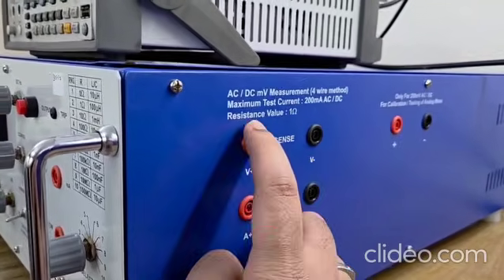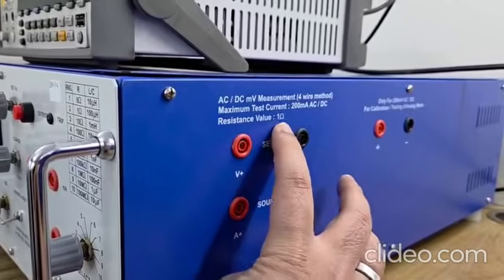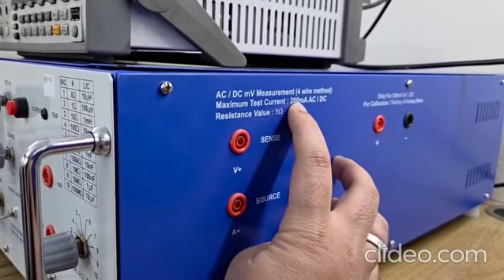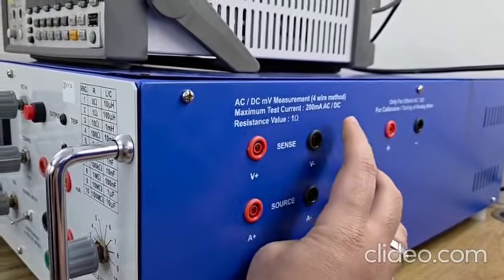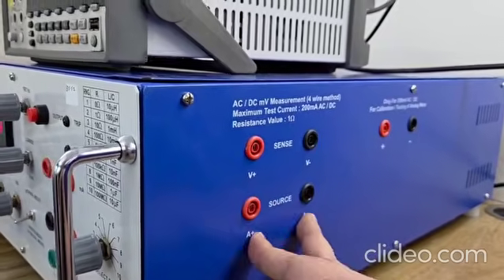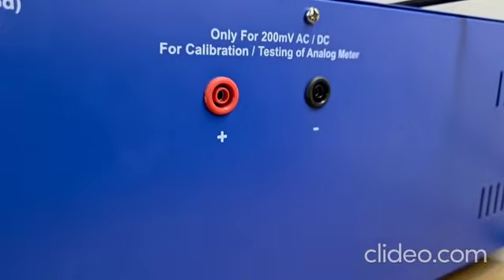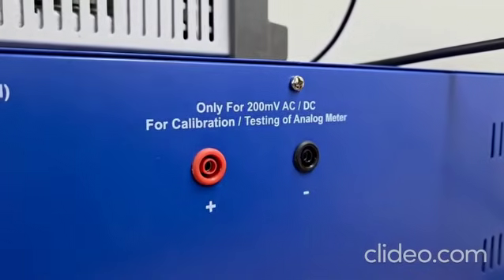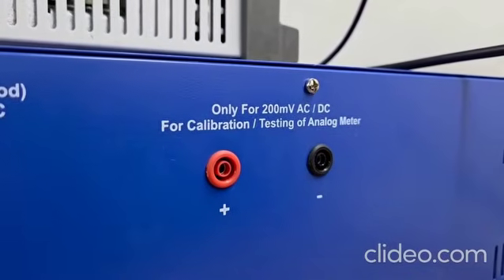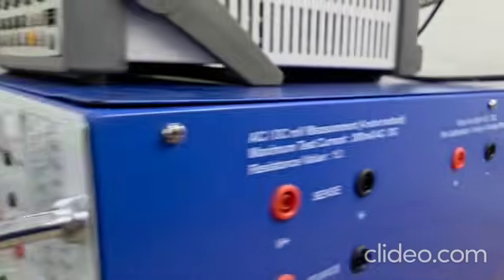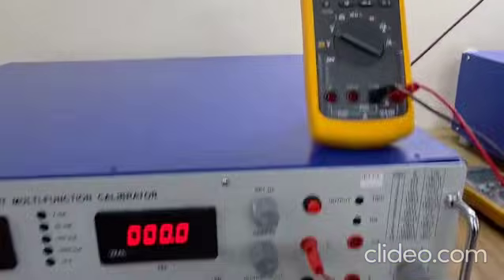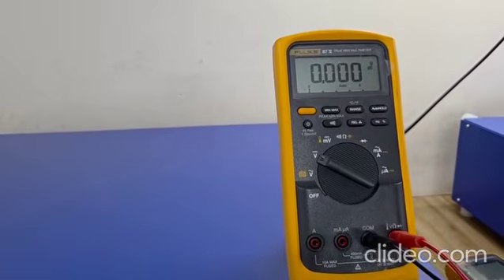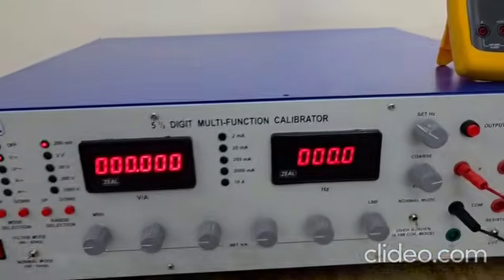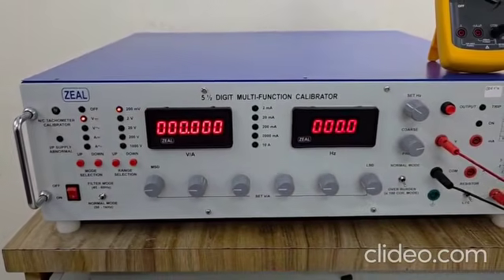In this, we have a small resistor of 1 ohm and test current up to 200 milliampere, both AC and DC you can source. And for analog meter calibration, these 2 are the points, only for 200 millivolt AC and DC. So now I will be calibrating this multimeter using the 5 1/2 digit multi-function calibrator.